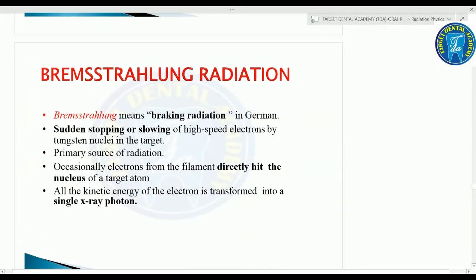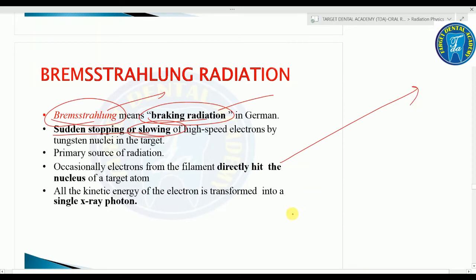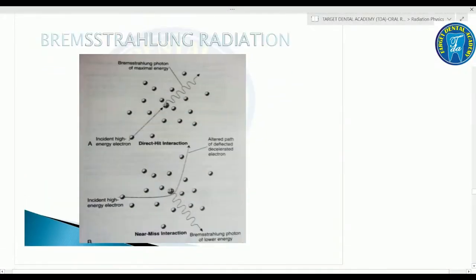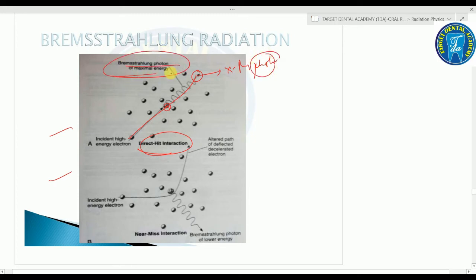Bremsstrahlung — from the German meaning 'braking radiation' — involves the sudden stopping or slowing of high-speed electrons by the tungsten nuclei in the target. It is the primary or major source of radiation. Two situations: first, a direct hit — if a high-speed electron directly hits the nucleus of the target atom, all its kinetic energy is transformed into a single X-ray photon, which is the Bremsstrahlung photon of maximal energy.